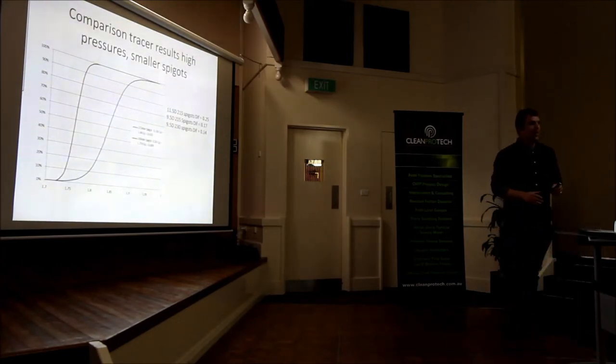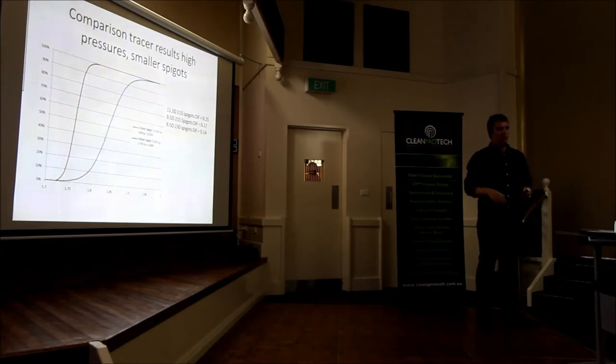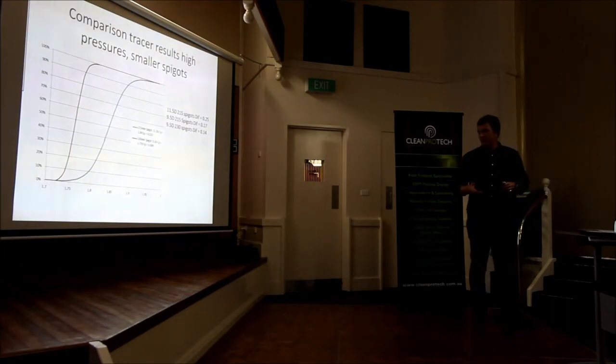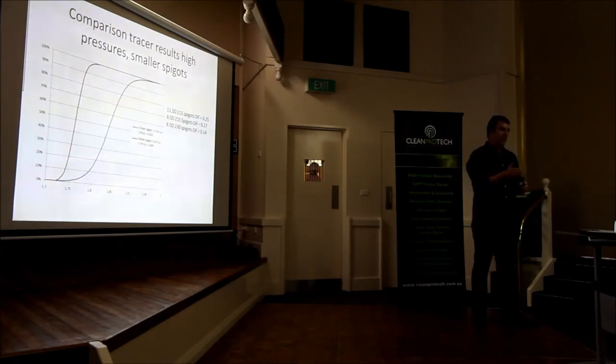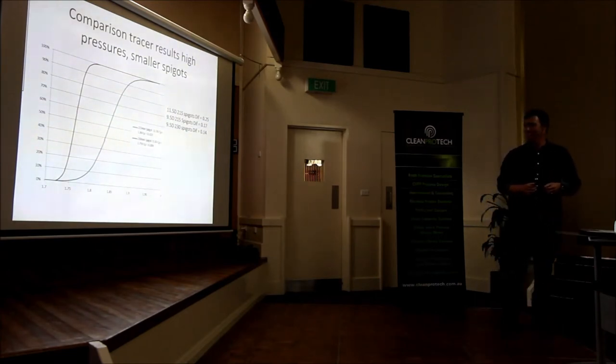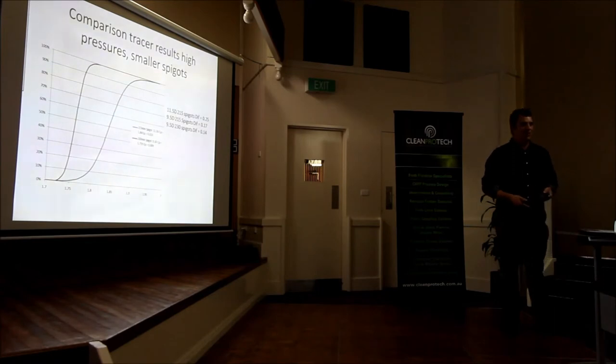Further on to all this — back when I had those results on our secondary circuit, which was that graph showing really wayward results: the pressure gauge was faulty, but there was also a difference in differential between each sump — one was at 0.15 and the other was at 0.20. When we got them the same and brought the one at 0.20 back to 0.15, I put that into our models which showed a yield decrease. Not really ideal, but we had an ash decrease as well, so we were sending better quality thermal coal out. It turns out our reliability team had been doing a lot of work with the pumps and motors and had upgraded the motors on one of our secondary circuits.